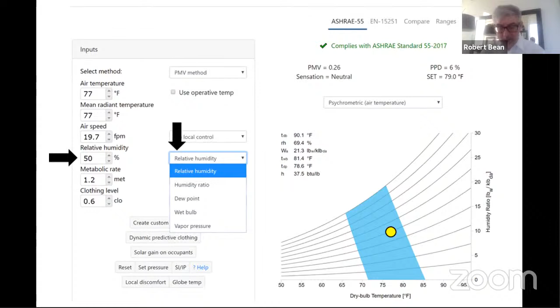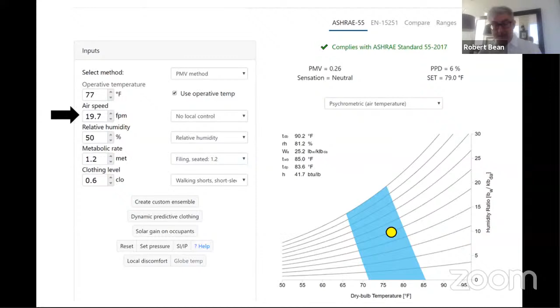And we've looked at it in terms of can we use airspeed, elevated airspeed specifically, for improving comfort. And we have now added a tool in there that allows us to look at elevated airspeed. So we do know that if we find that the architecture results in high mean radiant temperatures and that our mechanical systems can be conservative, allowing air temperatures to rise in the cooling mode, we can compensate for these less than ideal performances by elevating the airspeed. But we also know that airspeed can cause discomfort.